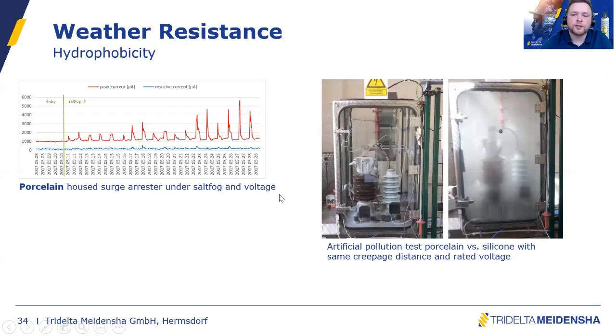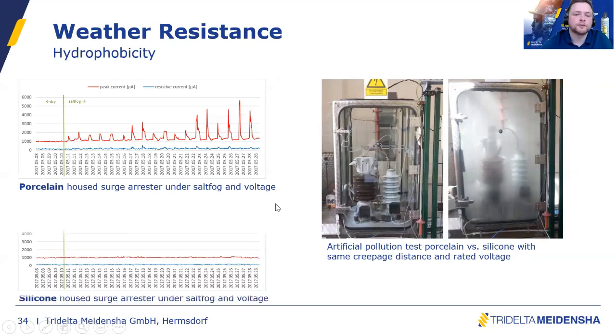And now I show you the same diagram at the same time for the silicone housed surge arrestor. There are no spikes. So the surface is non-conductive, and this is a very, very clear confirmation of the hydrophobic effect of the silicone housed surge arrestor. You only see MOV current, 1 milliamp standard.